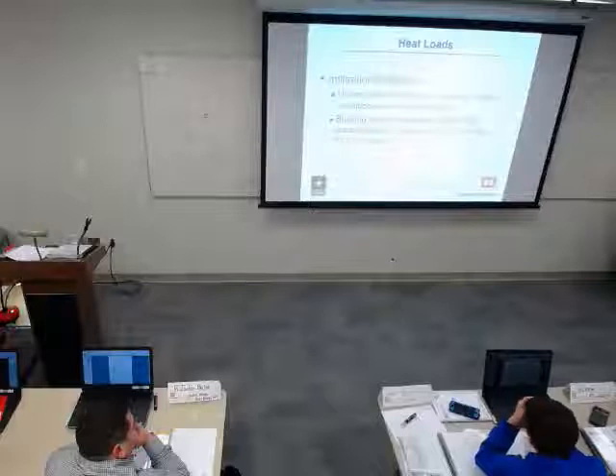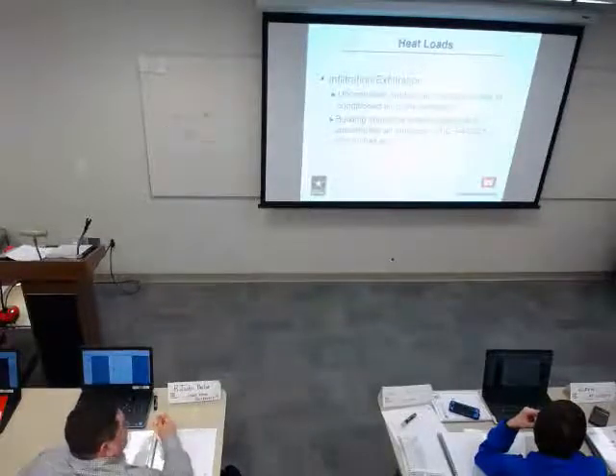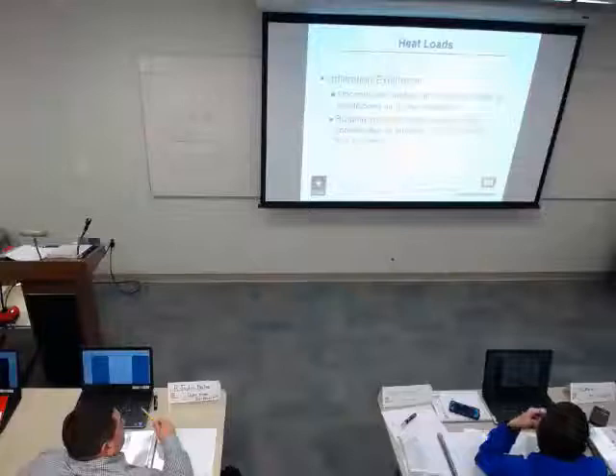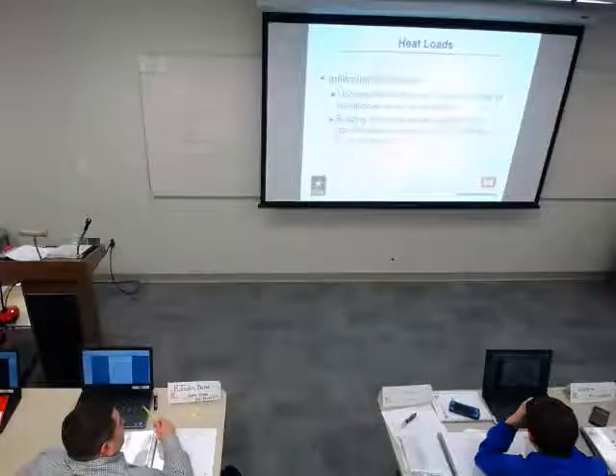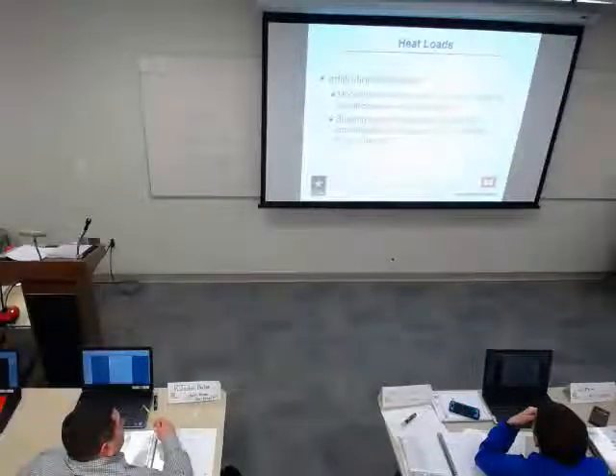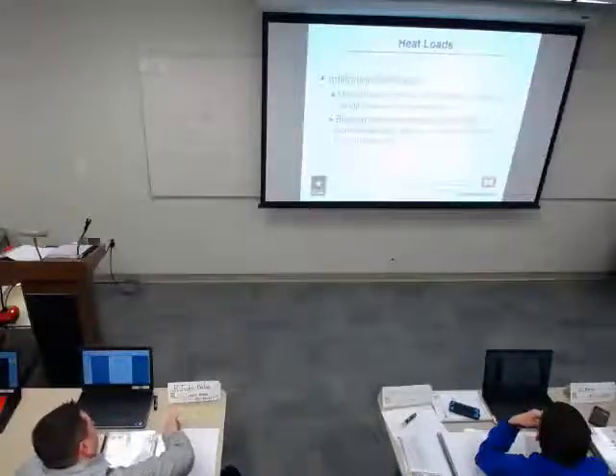Too high, and it's hard to get doors to close or stay closed. We start running into problems with the NFPA requirements that have to do with forces on doors. So that's another consideration. Not a part of this course, but that's where the 0.02 inches comes from. That's about the minimum we'd expect to see. Something that should, in my opinion, always be checked. It's easy to do. The last step of your TAB is to see that your building is positive, and you need to be sure that before you go into things, you talk to your TAB guy about how he plans to do that.